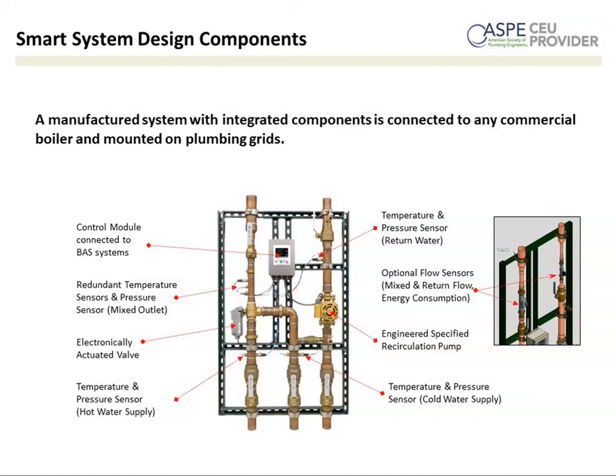We talk about plug and play, and that's the type of system that we look at here. The contractor, the installer, makes basically 5 water connections, brings 110 power to the unit, and the commissioning is very, very quick. The system essentially auto balances, right? All the playing around with circuit setters and ball valves and balancing during low demand or zero demand conditions goes away. So you talk to a lot of contractors, they really like these types of units because they make installation and commissioning very, very easy.